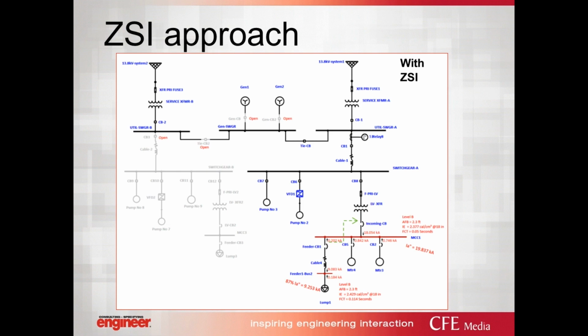Now, the result, as you see here, is that we reduced from 15.7 calories per centimeter squared to much lower, to 2.38. Now, the FCT time is 0.05. Therefore, we are reducing the incident energy at the bus because we were able to maintain the coordination by a delay of 250 milliseconds. If there is a fault at the load side, even though the incoming breaker instantaneous is enabled, the feeder breaker still has the time delay that we put there, which here is 250 milliseconds.